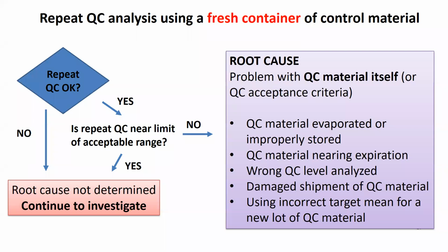So the lab can investigate these issues by performing activities like checking the QC vial liquid level, checking the QC open vial expiration date, checking the expiration date of the unopened QC material, check to see if it's a new shipment, check to see if you're using the correct target mean for a new lot of QC materials. So you want to repeat the analysis using a fresh bottle of QC. If the repeat passes and is not near a limit of acceptance, then the root cause is likely an issue with the QC material itself. If the repeat passes, but only barely so, and is near a limit of acceptance, then the problem is not likely due to an issue with the QC material itself, and further investigation is needed. If the repeat fails, then the root cause has not been determined and troubleshooting should continue.